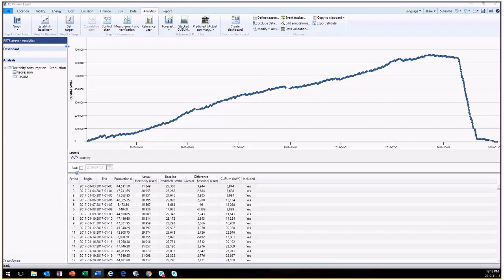When looking at the end-to-end CUSUM, periods with a straight line represent periods of consistent energy consumption, while inflection points are times when the slope changes, indicating times when the energy intensity changed. Generally, periods with consistent energy use, the straight lines, make for better baseline periods and can provide some guidance in selecting the right period, but it still needs to serve the purpose you need.